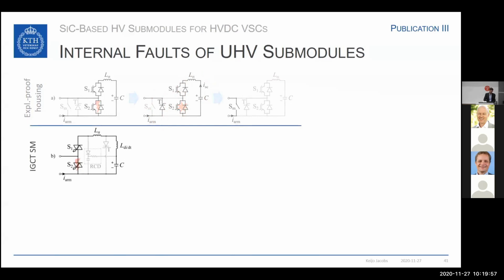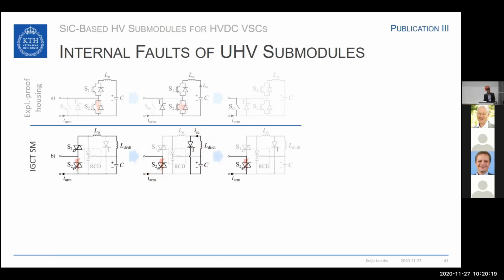If we use a submodule with IGCTs, we can take a different approach. IGCTs have a short circuit failure mode, which is stable. Therefore, the arm current can be conducted through the failed device. And the capacitor energy can be discharged through a bypass thyristor, which is arranged across the inductor and the capacitor. However, for higher submodule energies, that can also be critical.